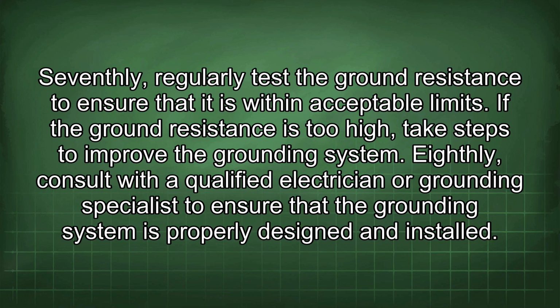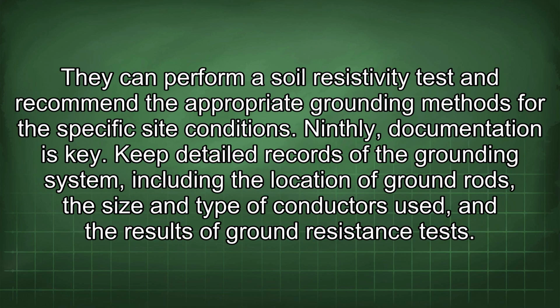Eighthly, consult with a qualified electrician or grounding specialist to ensure that the grounding system is properly designed and installed. They can perform a soil resistivity test and recommend the appropriate grounding methods for the specific site conditions. Ninthly, documentation is key. Keep detailed records of the grounding system, including the location of ground rods, the size and type of conductors used, and the results of ground resistance tests.